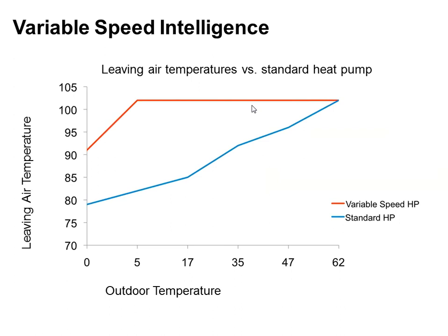Now, with that being said, we can only do that to a certain point. In this example on this chart, when we get down to like 6, 7 degrees outside, we've slowed down the blower as much as we can. We've ramped up the condensing unit as much as we can. The only way to get more BTUs at that point is to start speeding up the indoor blower, at which case you see the discharge air temperature start dropping. However, by the time we get below 10 degrees outside, we are probably already switched over to our gas furnace or electric supplementary heat anyway, so it's pretty much a negligible point.